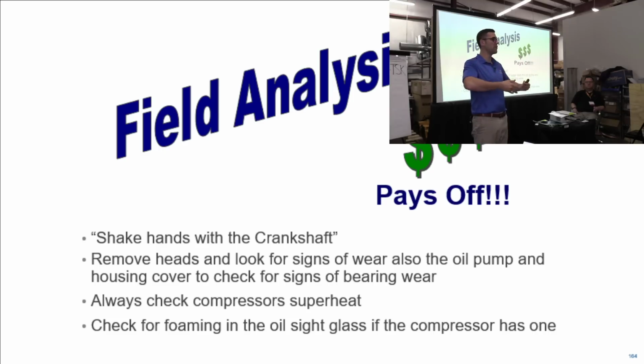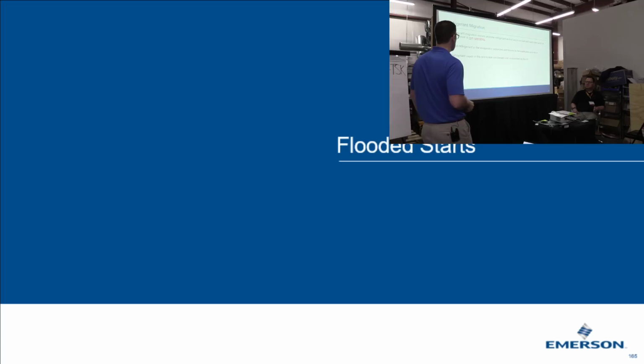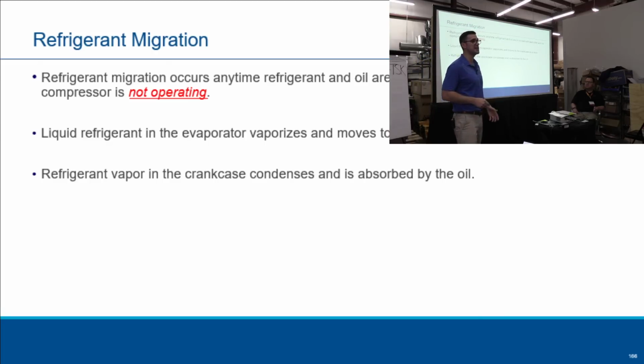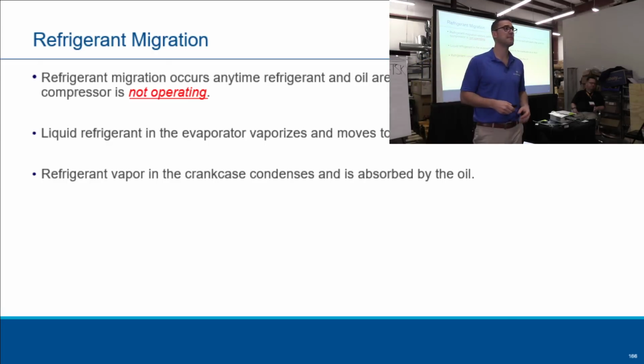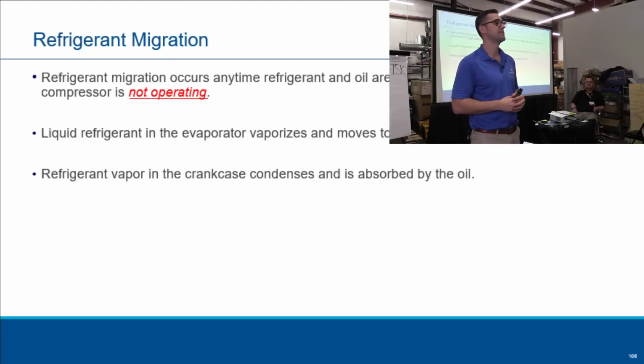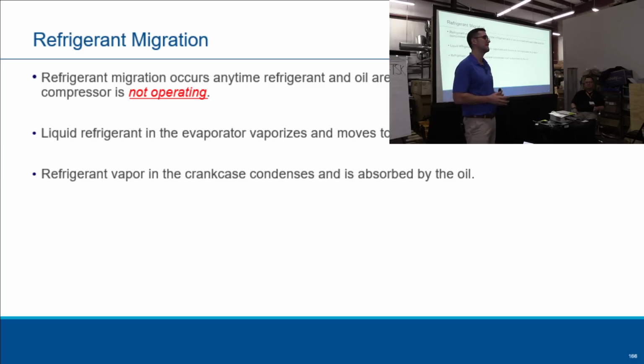Is the evap coil dirty? Is the TX valve faulty? Is it set in properly? Okay, flooded starts. What's a flooded start and how does it happen? When liquid refrigerant migrates to the crank, I think it's the crankcase, right? Exactly. Starts, then the liquid expands rapidly and washes out all the bearings. 100%. Thank you very much.